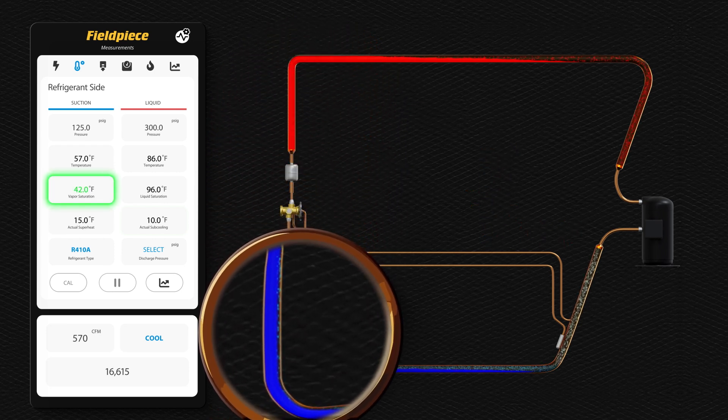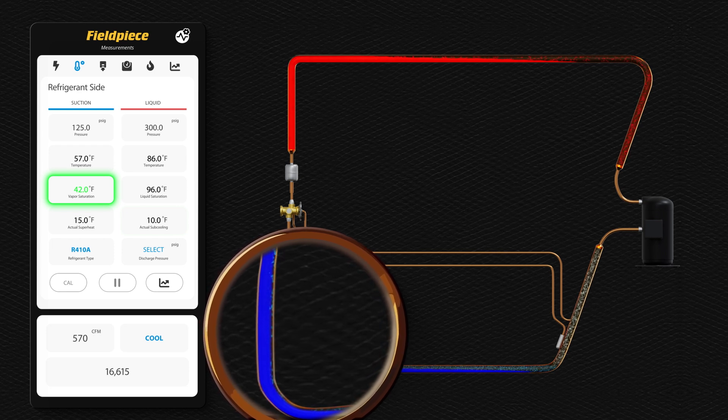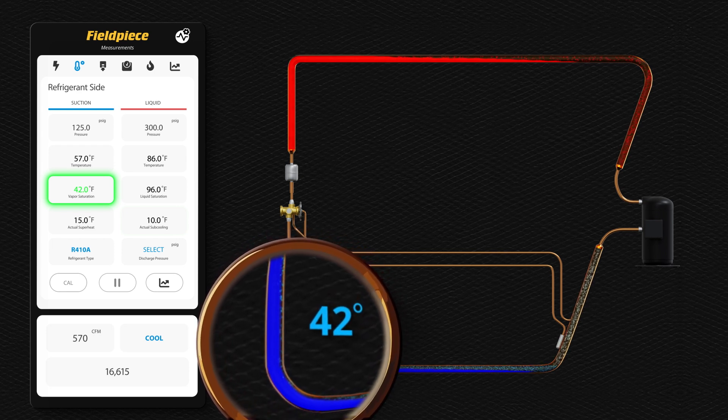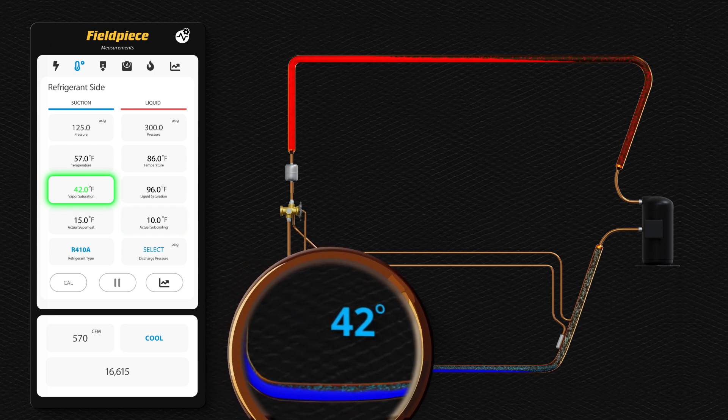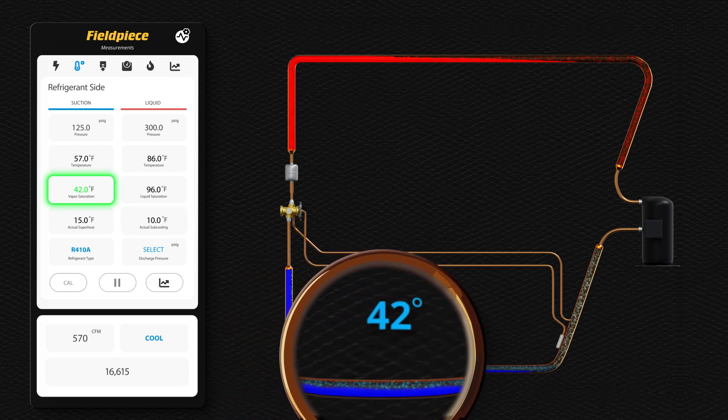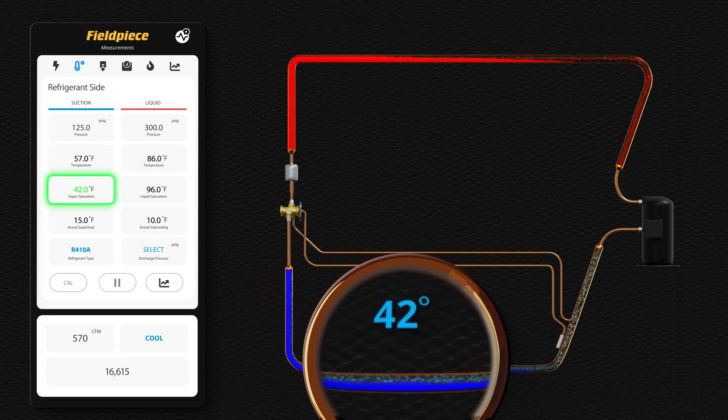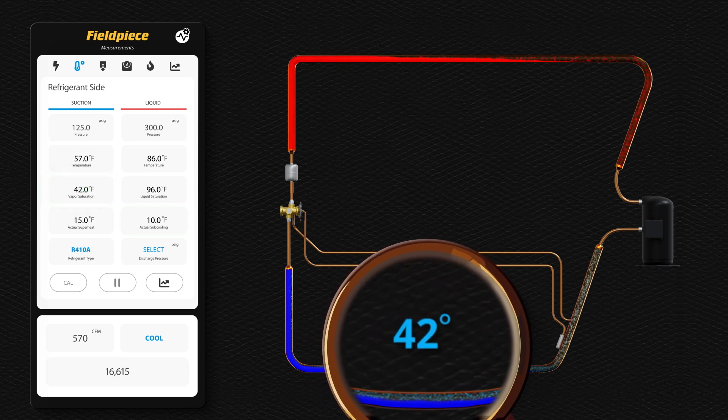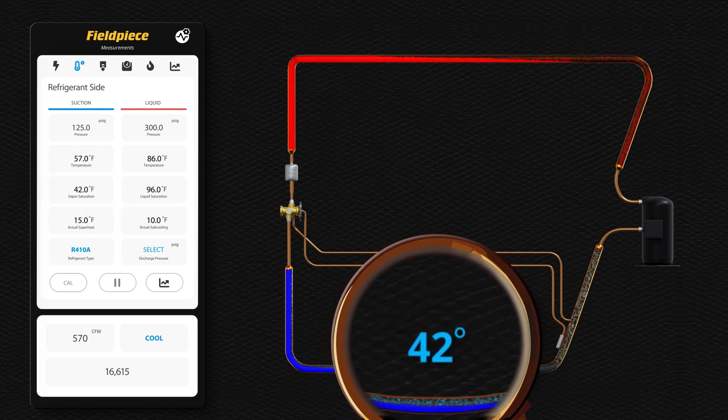The Fieldpiece app shows the saturated evaporator temperature equals 42 degrees. In the evaporator, whenever vapor and liquid exist, the refrigerant temperature will be 42 degrees. Any heat absorbed will only assist in a phase change from liquid to vapor, but the temperature will remain 42 degrees.